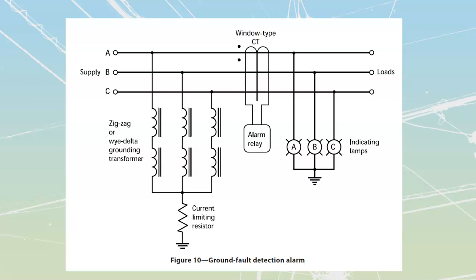What we would see is an A and an A together, a B and a B together, and a C and a C together for the phases that are connected across there. This creates that neutral point inside of there. Normally, we shouldn't have anything flowing back through here. Here's the neutral point, and what we've done is taken this neutral point and put a current limiting resistor across the bottom of it.